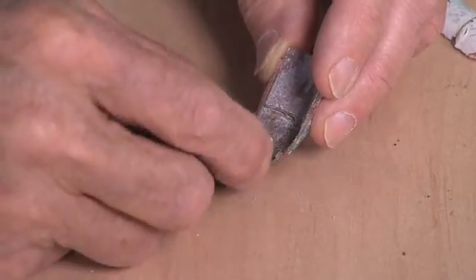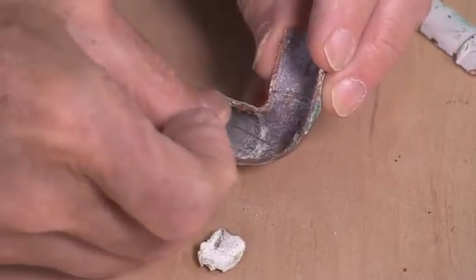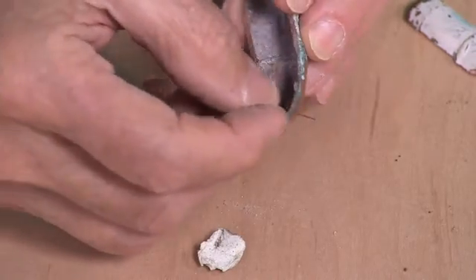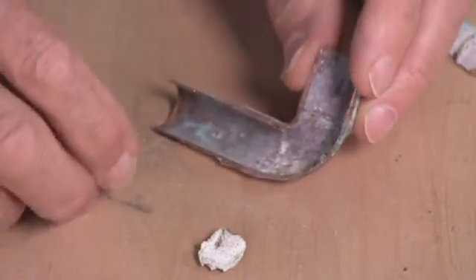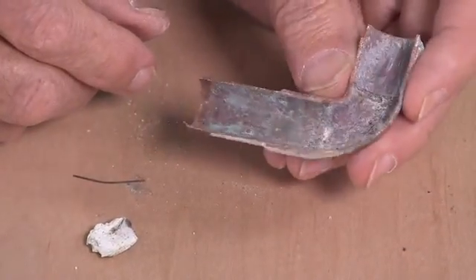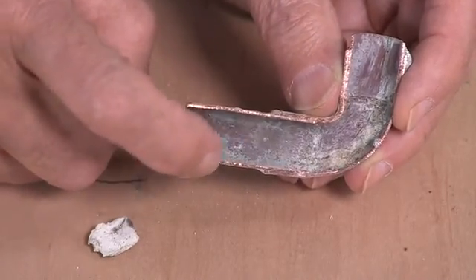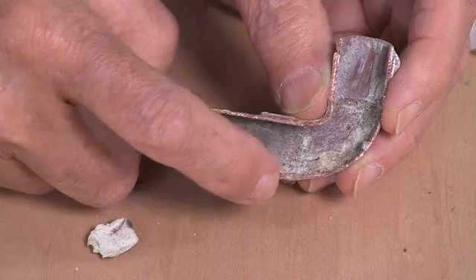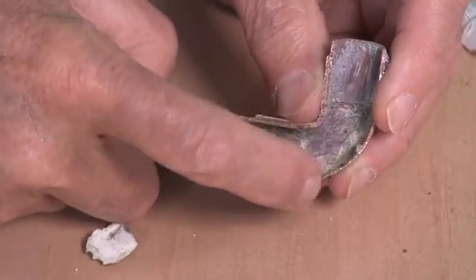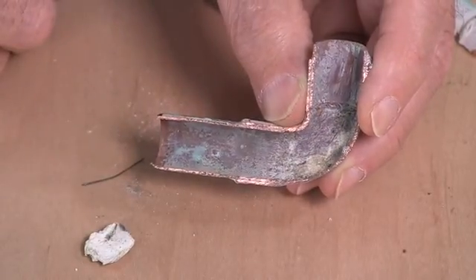of minerals. And then when I looked really hard, I was finally able to spot that there was a hole in there that we couldn't see very well. And if you look here, I want to show you one thing. If I hold this just right, I think you'll see the thickness of the wall right here. That's the good pipe up above. It's thicker here where there's 2 pieces that are together. And then you can sense it's starting to get thinner. And it actually is less than half the wall thickness down here.